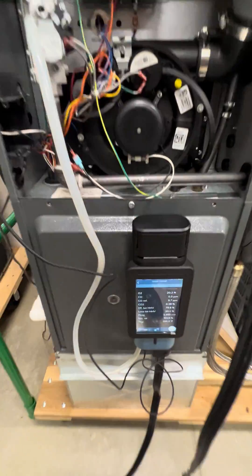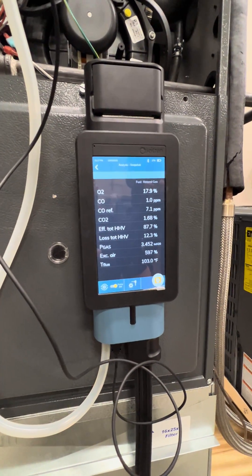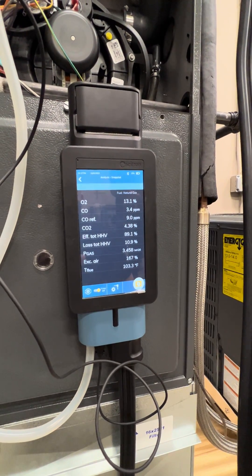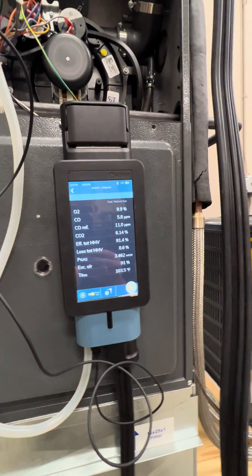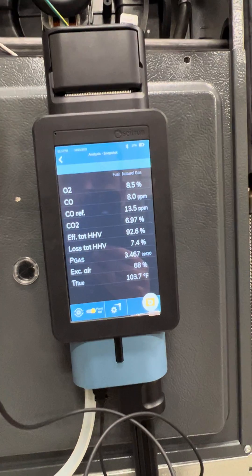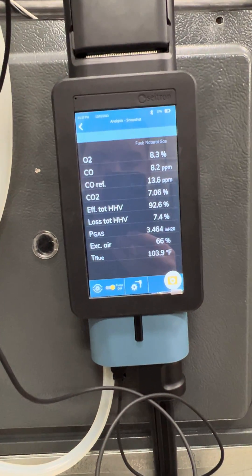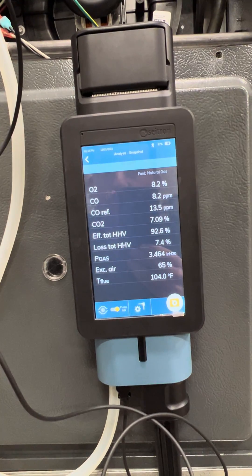As we have the probes in the stack, we can see our combustion readings are changing. Oxygen is dropping down — now we're at 13%. Carbon monoxide is about 3.4 parts per million. You can also see we have our carbon monoxide air-free reading. Your CO air-free reading will always be higher than your normal carbon monoxide reading because it removes the diluting effects of all that excess air. Now our O2 is at 8.3% and combustion efficiency is at 92.6%.